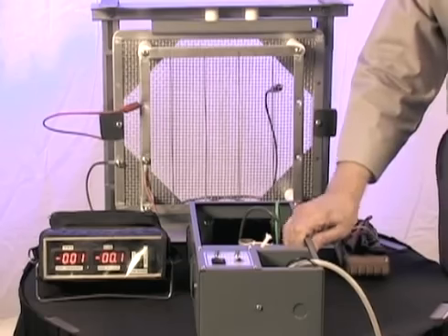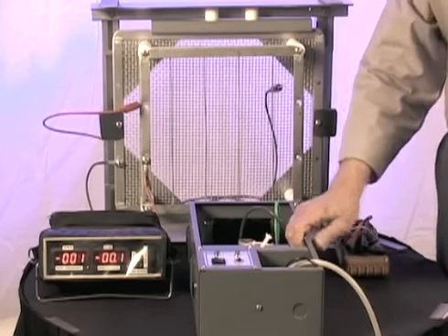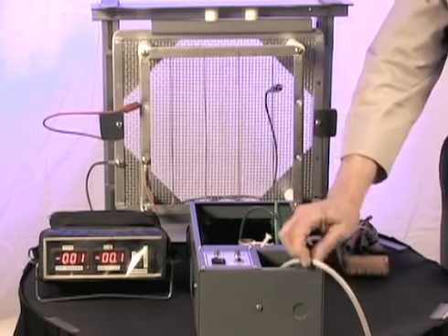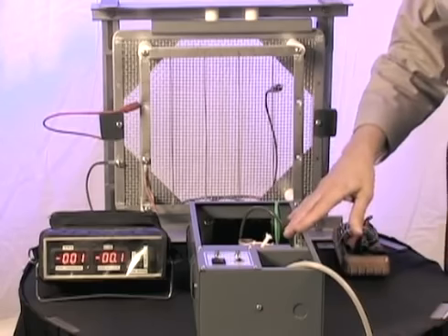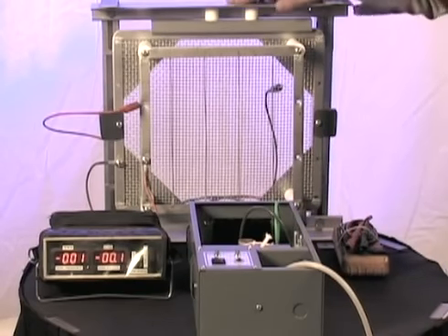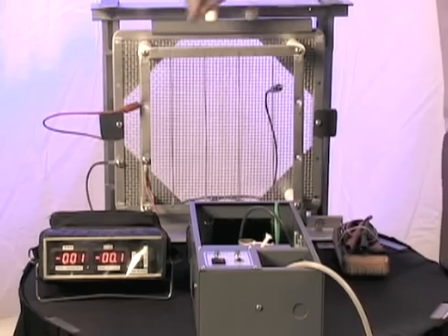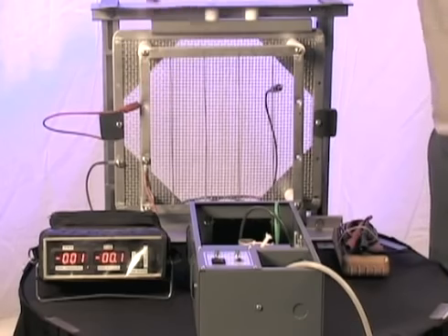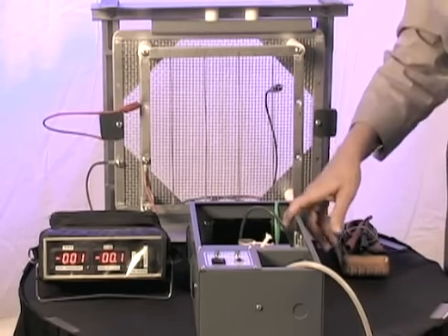Troubleshooting these systems comes in 3 sections. Either you have bad incoming power, there's a problem with the generator itself, or there's a problem out at the electrode set, or the wires that supply the energy to the screen set from the generator.